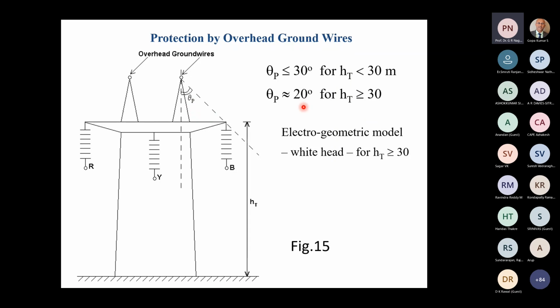This angle we have discussed at length when considering single poles, and also when considering Franklin rod design earlier. The same principle is applied here. If the height is more than 30 meters, this angle is 20 degrees. Otherwise, it is 30 degrees. So now, suppose the lightning were to strike here, it should be prevented from going here. Therefore, this conical angle must be less than this protective angle. That's the basic, very simple principle. Either the geometric or the electrogeometric model is applied here.